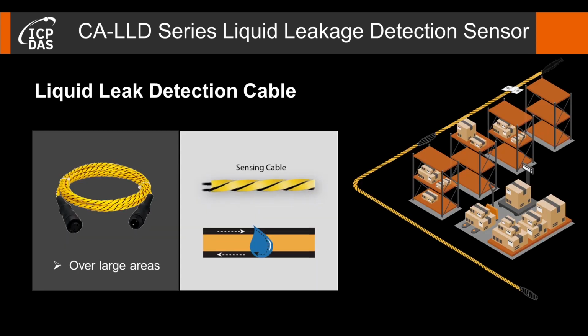The liquid leakage detection cable can be used to detect leaks over large areas. For example, in the case of data centers, to monitor water leakage in the data center, the client chooses a detection cable as the detector. In addition, the liquid leakage detection cable contains two sensing cables, and the leaks must touch both sensing cables at the same time for the alarm to be triggered.